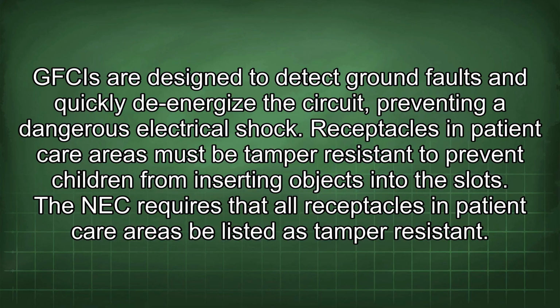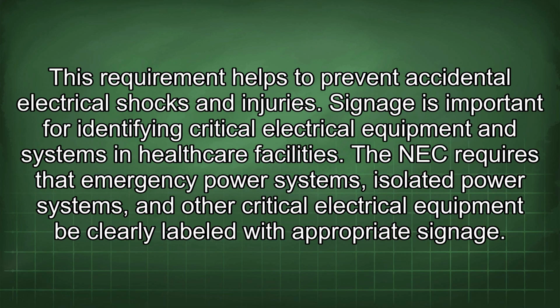Receptacles in patient care areas must be tamper-resistant to prevent children from inserting objects into the slots. The NEC requires that all receptacles in patient care areas be listed as tamper-resistant. This requirement helps to prevent accidental electrical shocks and injuries.